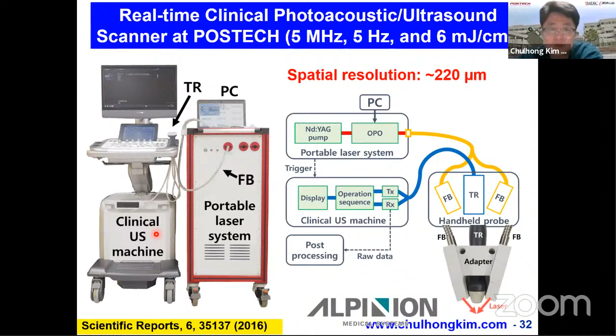At the same time, we should be able to get the acoustic signal in raw data form, because all this ultrasound imaging system is based on transmission and reception. Beamforming is based on the round trip of ultrasound, but we only receive the ultrasound. In that case, our beamforming method should be changed. So with this particular system, we can program our sequence ourselves. So this is a kind of special ultrasound imaging system.